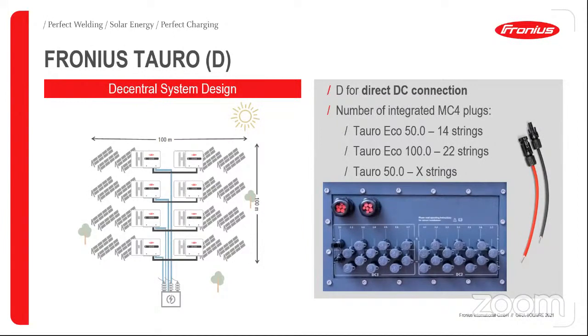In this option, we have this direct connection to the inverter with these MC4 plugs and with this different number of connection. So for instance, in the Eco 50 kilowatts, we have 14 strings input, and for Tauro 100, we have 22 strings. All of these strings can be monitored in our system individually. So we see here that in the DC connection of the inverter, we can connect directly our cabling from the DC side with MC4 directly to the inverter. This inverter has an CE certification. This is the European certification, and we are allowing this inverter for all the markets in Colombia.